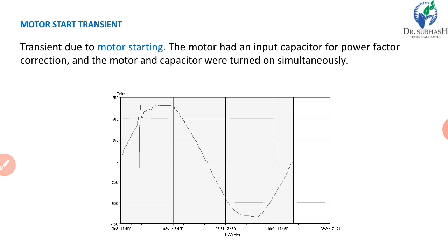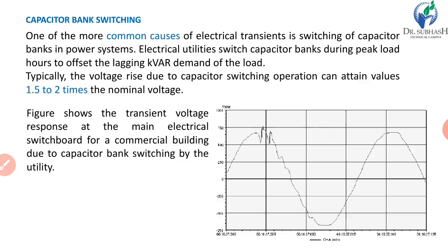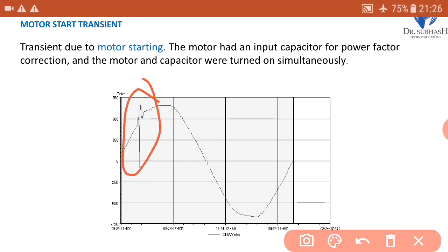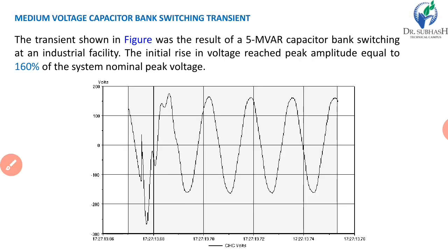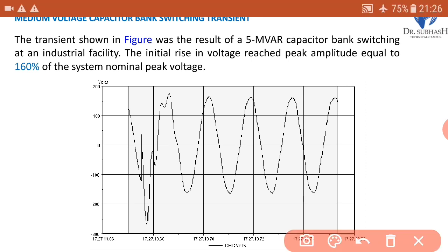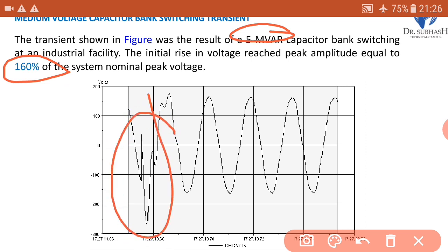Motor start transient. We have seen that at starting, the motor current may be 5 to 6 times the normal rated current. During starting, in this transient due to motor starting, the motor had an input capacitor for power factor correction, and the motor and capacitor were turned on simultaneously. So here we can observe this transient due to motor start. Now, medium voltage capacitor bank switching transient. The transient shown in the figure was the result of 5 MVAr capacitor bank switching at an industrial facility. The initial rise in voltage reached a peak amplitude equal to 160% of the system nominal peak voltage. So here we can see the transient.